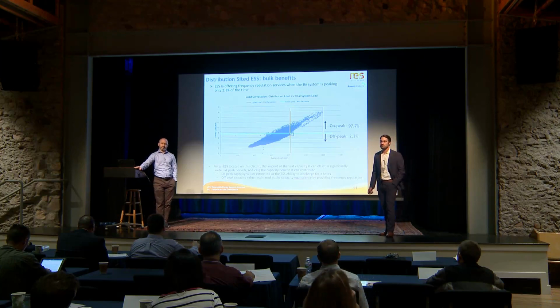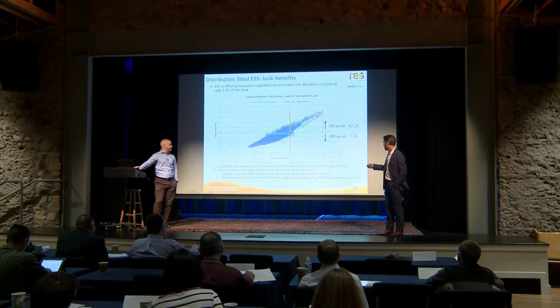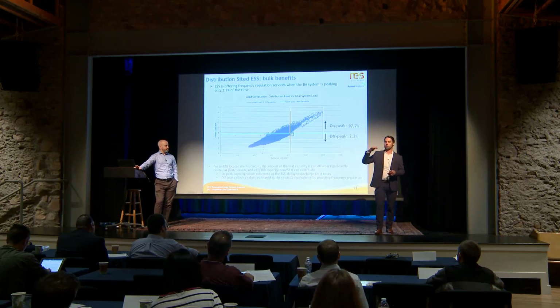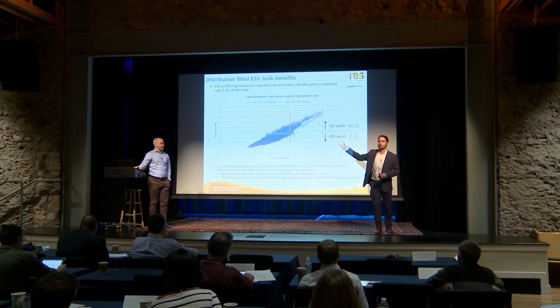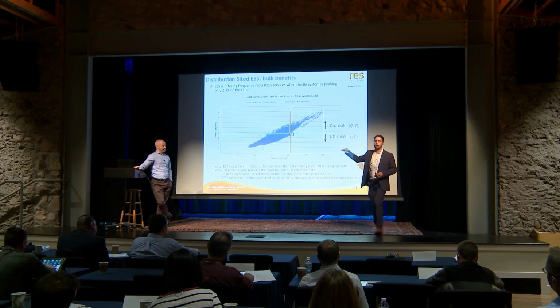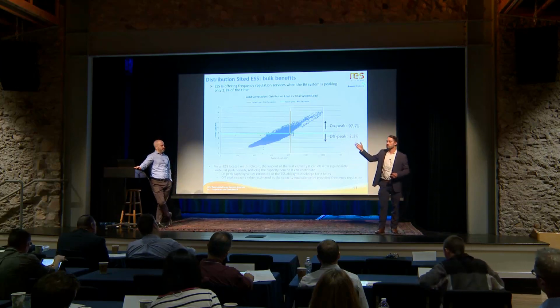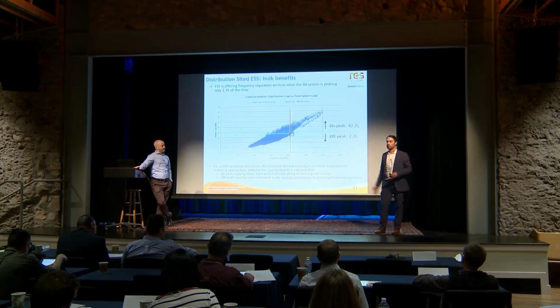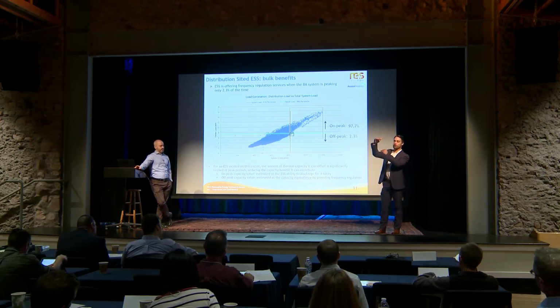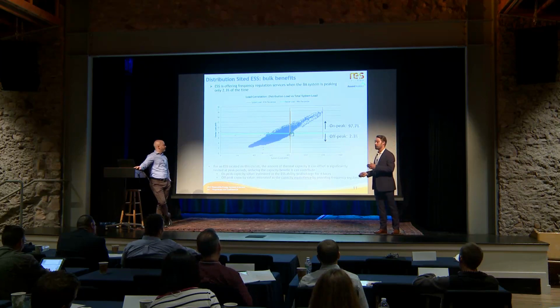The way we size these is, remember I said we're taking the battery out at the top 90th distribution load percentile. So we'll have a PT or something that measures the load. If it gets above the 90th percentile, then we take it out, right? So the way we size the battery is that 90th-to-100th percentile difference is how much we could actually regulate.